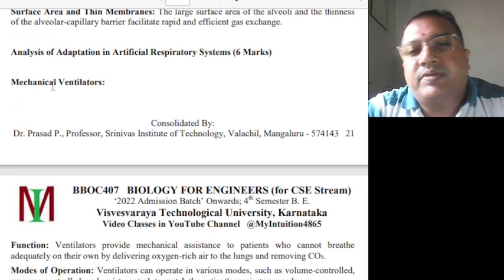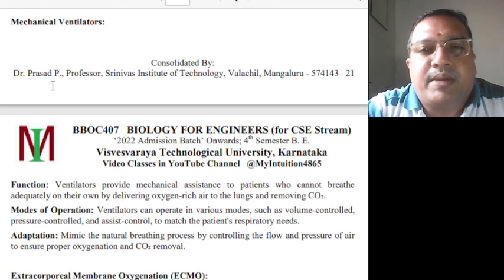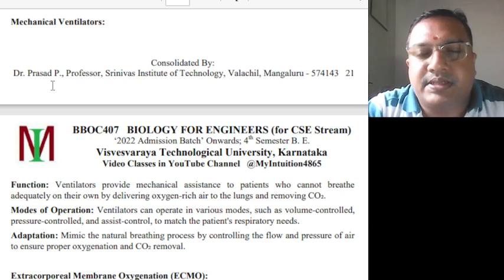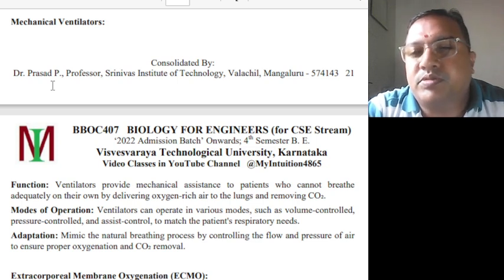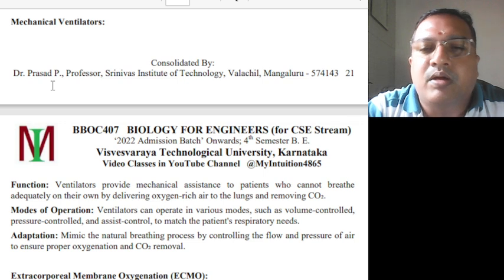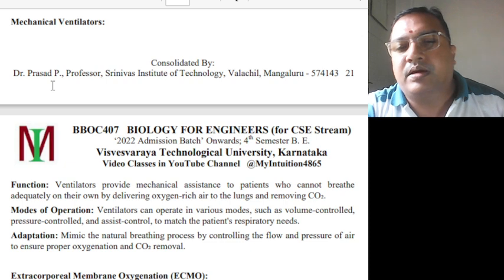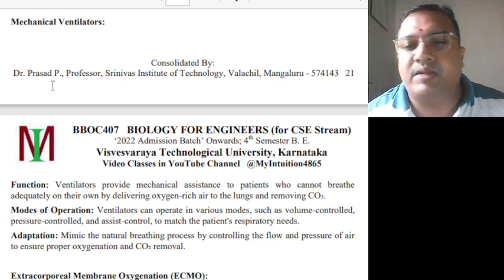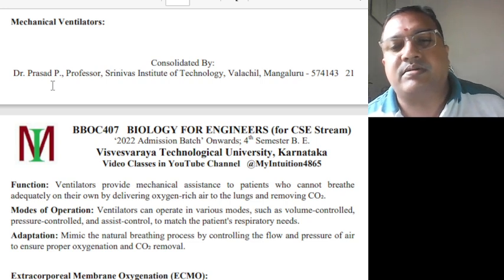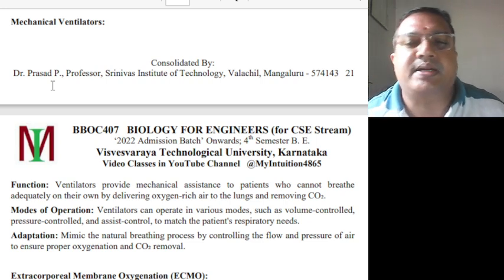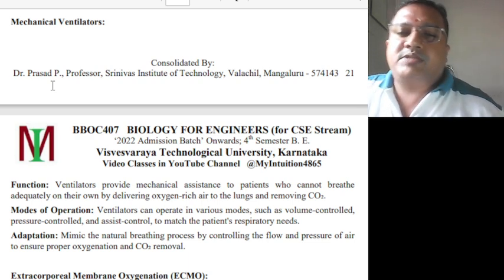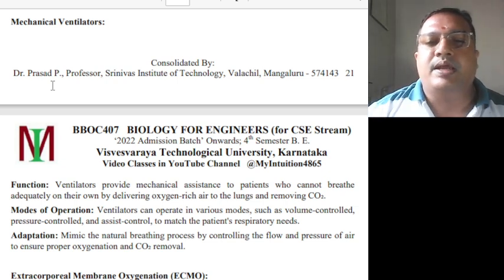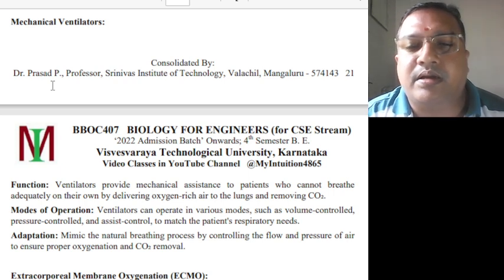Now for adaptation in artificial respiratory systems — for six marks. Mechanical ventilators provide mechanical assistance to patients who cannot breathe adequately on their own, by delivering oxygen-rich air to the lungs and removing carbon dioxide. Ventilators can operate in various modes such as volume-controlled, pressure-controlled, and assist-controlled to match the patient's respiratory needs, mimicking the natural breathing process by controlling the flow and pressure of air to ensure proper oxygenation and carbon dioxide removal.